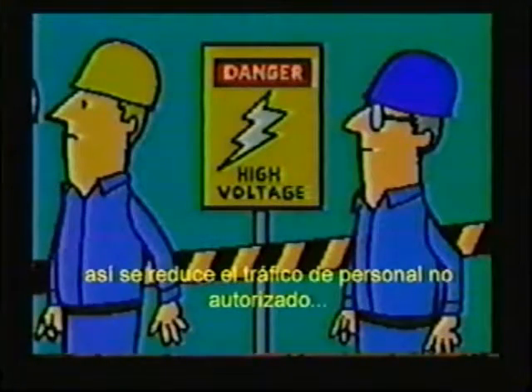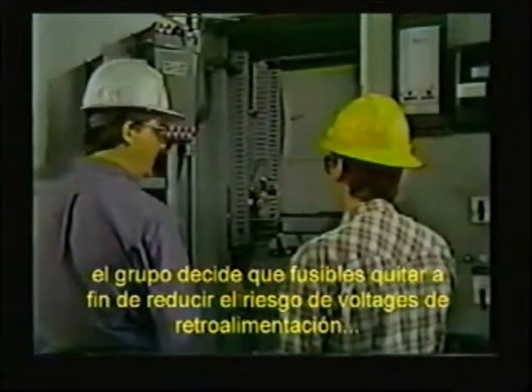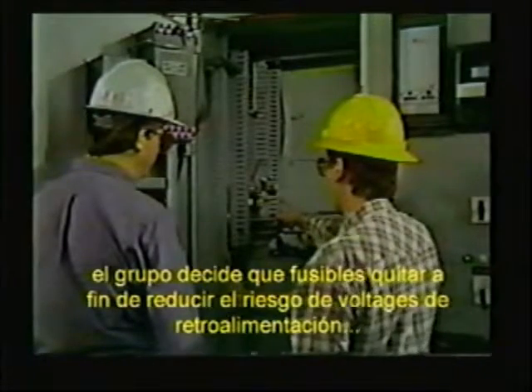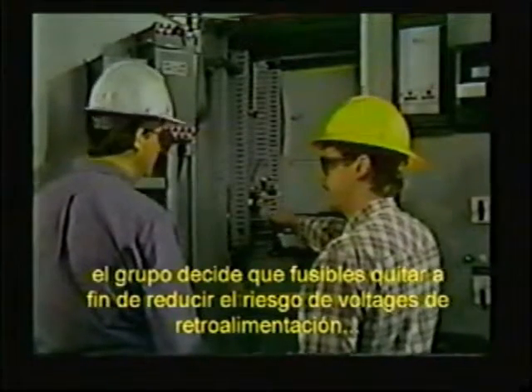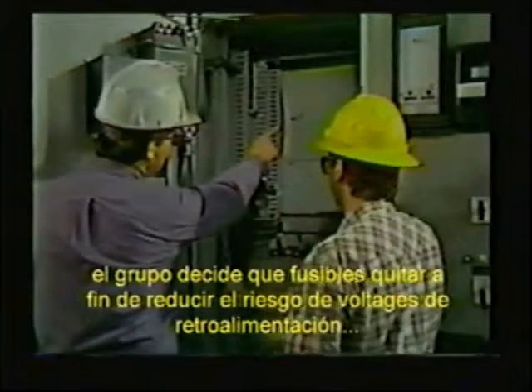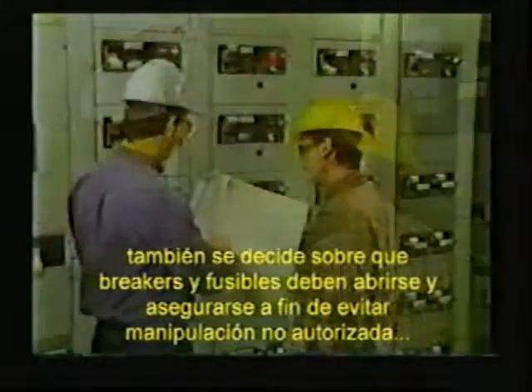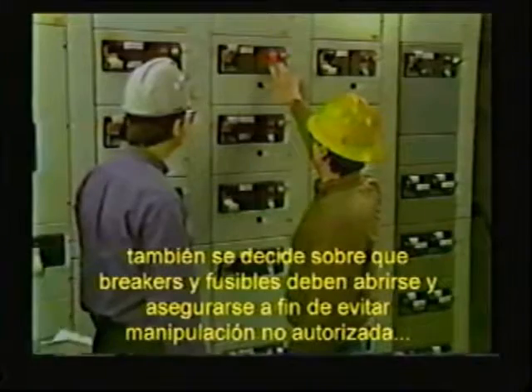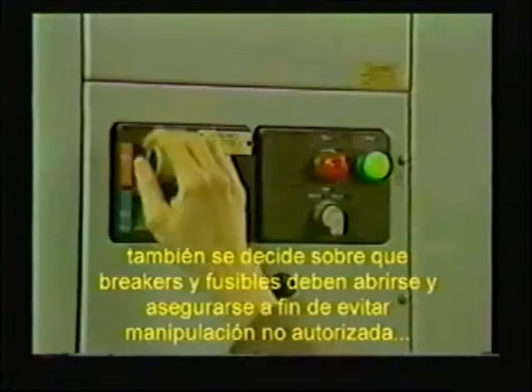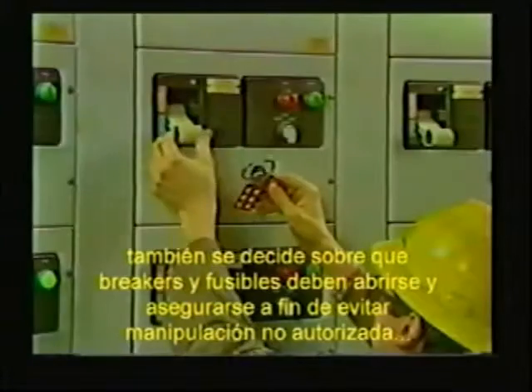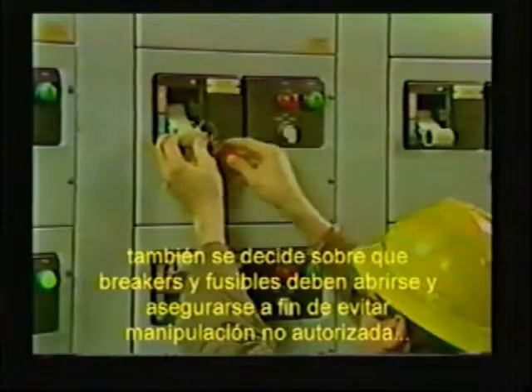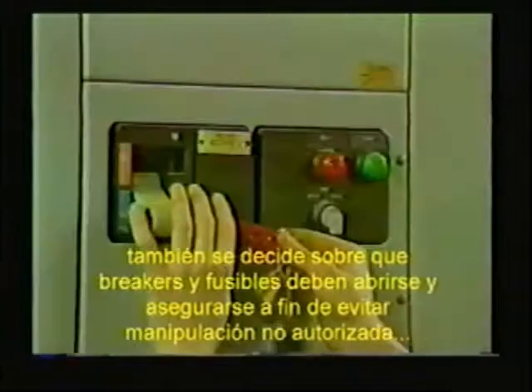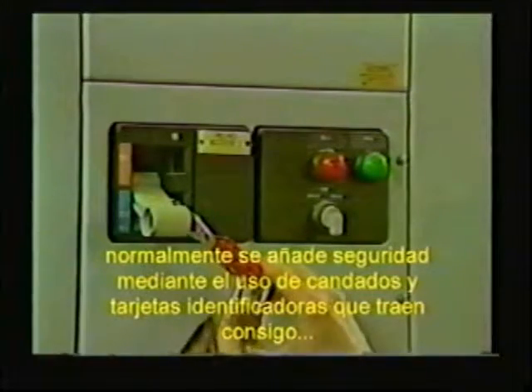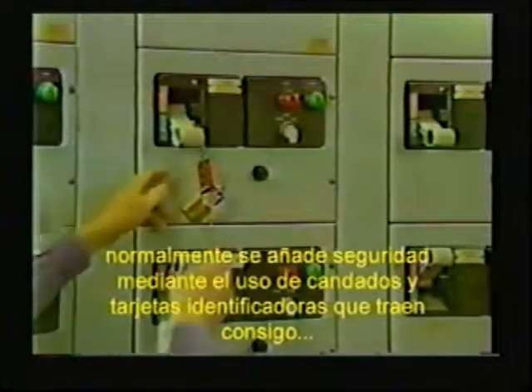In addition to keeping unauthorized personnel out of the area, it reduces the possibility of bumping into something he is trying to avoid. Dave and the plant engineer decide together which fuses and potential transformers should be opened to eliminate as many potential sources of power from the work area as possible. Next, they review which breakers and switches should be opened. Once opened, the plant engineer locks out the device and places a warning tag through the mechanism to prevent unauthorized use of the equipment. As an added safety measure, Dave also locks out the equipment using his own padlock and tag.